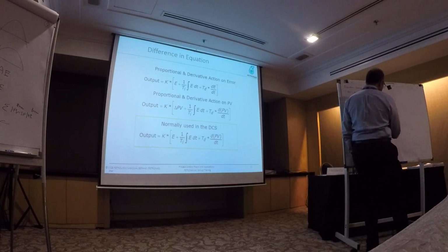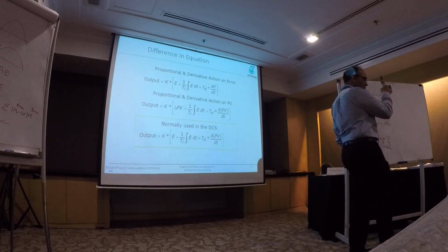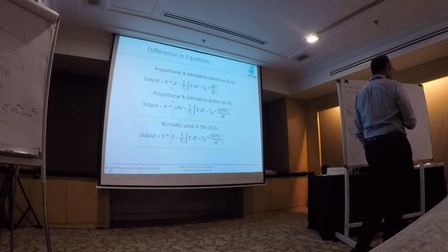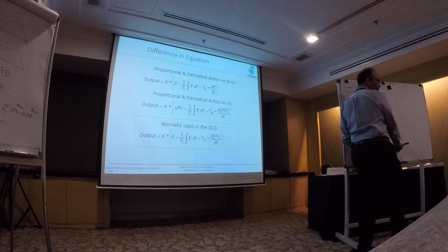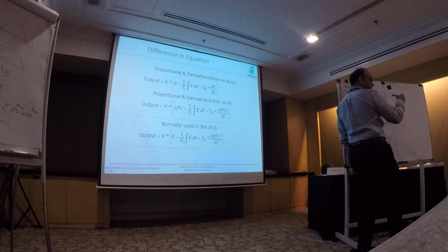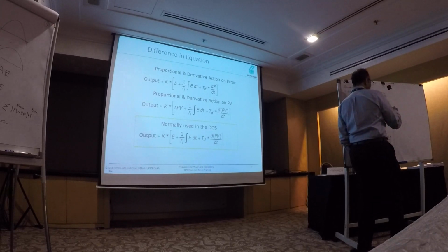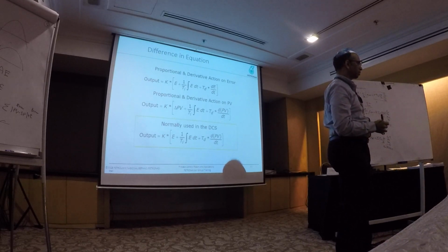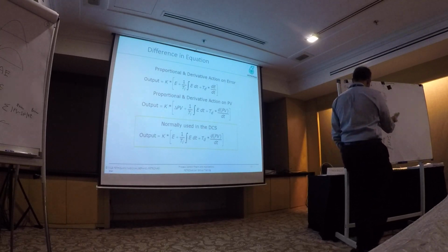So this is a configuration parameter. In Honeywell, you would go to the equation form, and you will actually see equation 1, 2, 3. So you select which one, whether it's equation 1, equation 2. In Yokogawa, that equation form will either be PID, PI-D, or I-PD. So you select I-PD. In the configuration page, you actually select. In Foxboro, you have to look for this particular parameter called SPL lag, and you either set it at 1 or set it at 0. I can't remember which one is which.